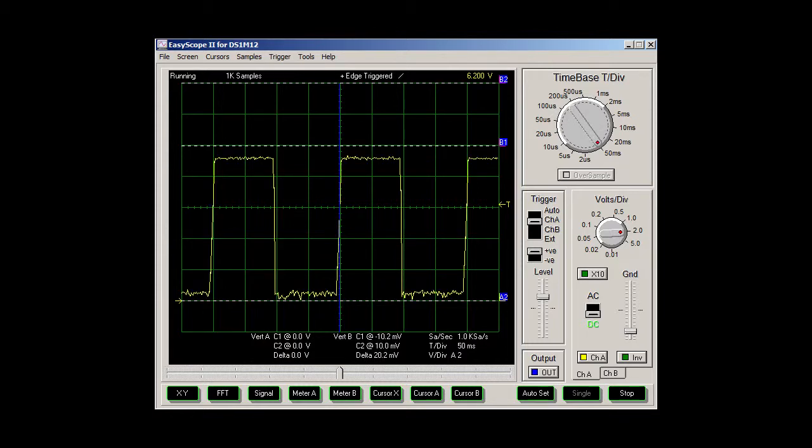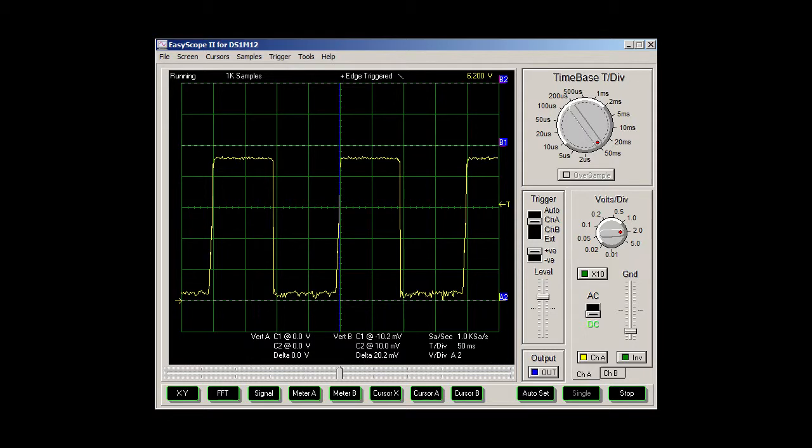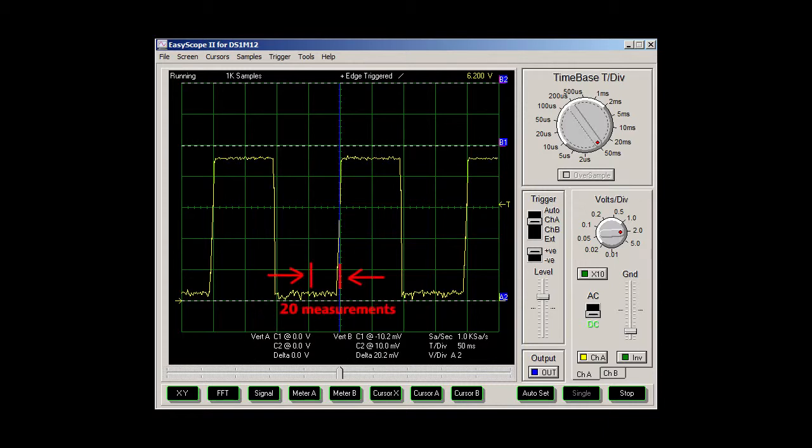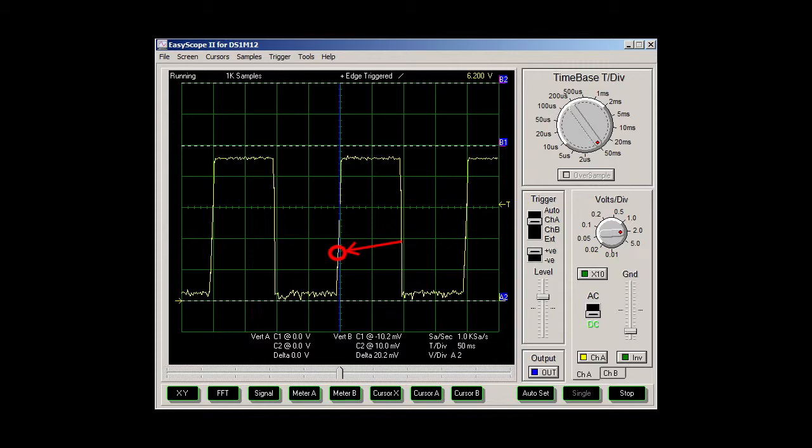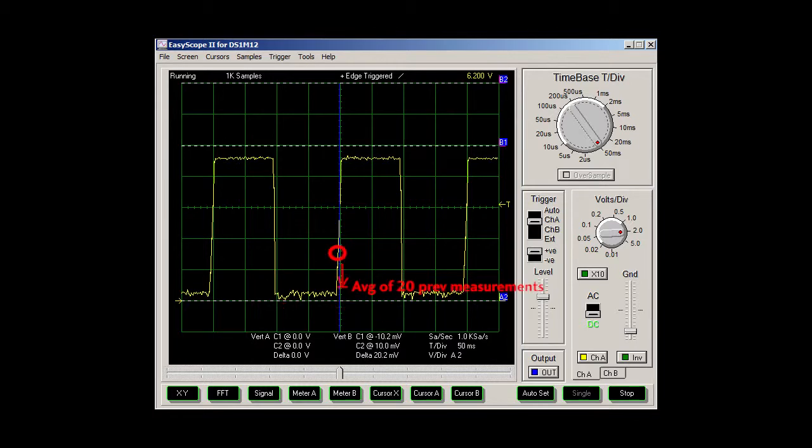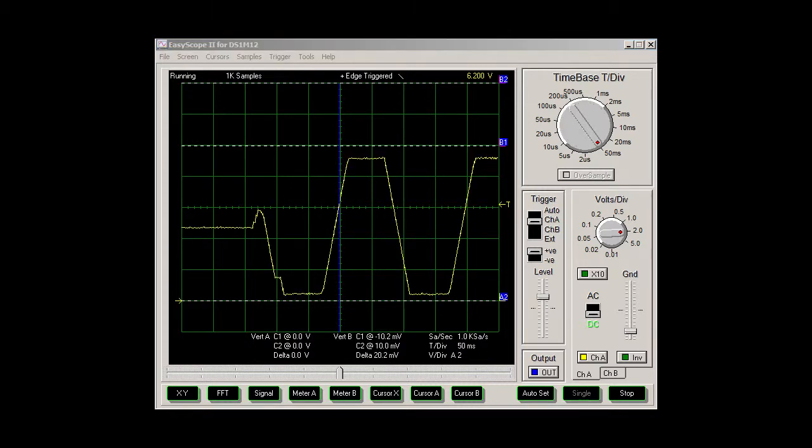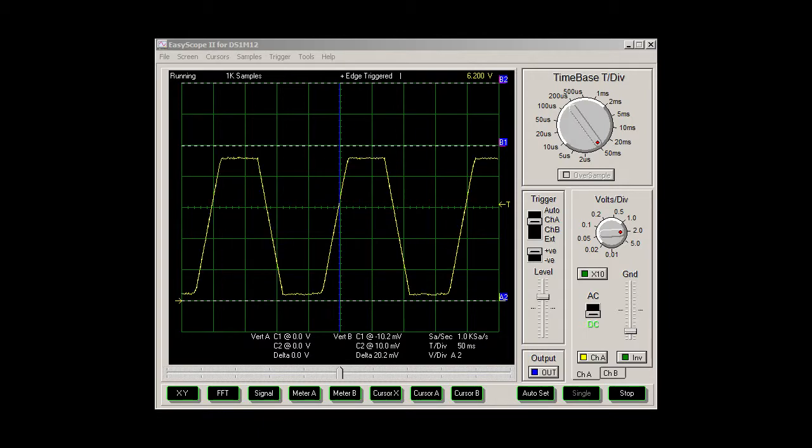There is a problem with that though. Let's keep increasing the filter size and see what happens. We know this signal is 100 measurements wide. What happens if I say I want the filtering to be 20 samples wide? The sensor averages the previous 20 samples and sends that out. That means this value that would normally be here is now the average of all these previous samples, so it's going to drop somewhere down here. We don't actually get the full value until way over here when we are averaging these 20 samples. What that does is it creates a slope like this, and if I change filtering to 20, sure enough that is exactly what happens.